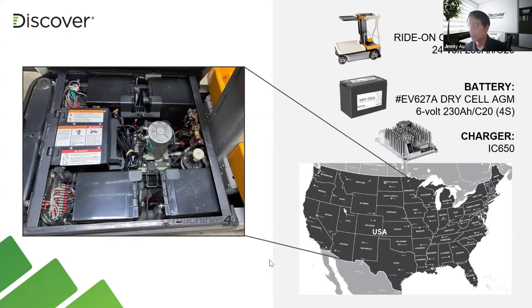One of the things I wanted to mention in this application is that there are a number of different chargers that can be used, but we feel the Delta Q is a good choice here because it has a feature called temperature compensation, measuring the overall temperature of the batteries, which is ideal. Jimmy and Discover can talk about how they recommend having temperature compensation control when charging sealed batteries, just so you get precise overcharge protection. That's one of the features and benefits, along with being small and compact enough to fit in a tight application like this.